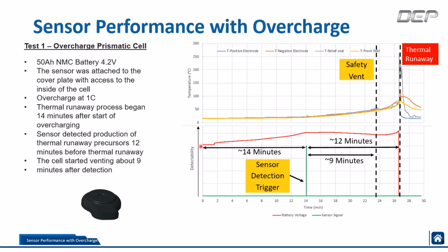And here we have the red line is the battery voltage, and this green line is our sensor signal. Now, in about 14 minutes from the start of the test, our sensor sent a detection trigger signal saying that thermal runaway is processing, or it's detecting some degradation inside the cell. 9 minutes after its detection, the safety vents of the prismatic cell came off, and 3 minutes after that, the thermal runaway occurred. So we were able to detect a full 12 minutes before that thermal runaway.